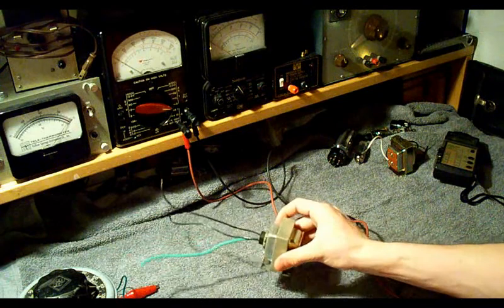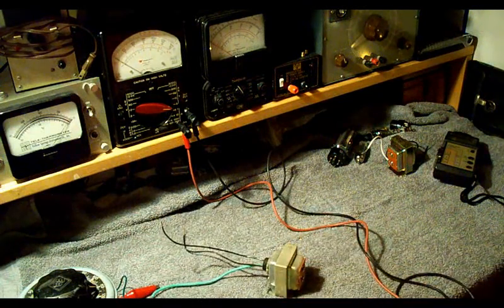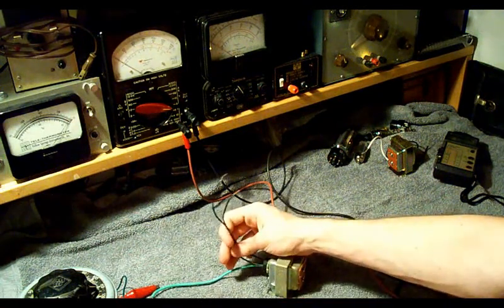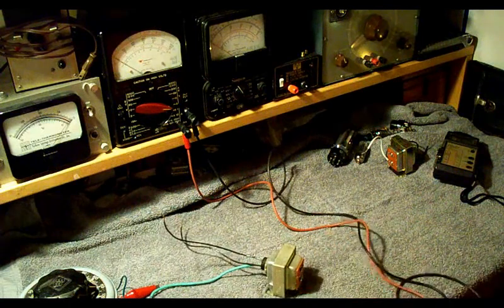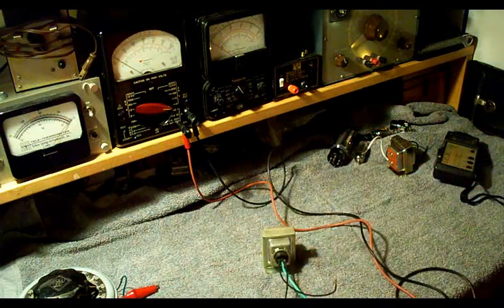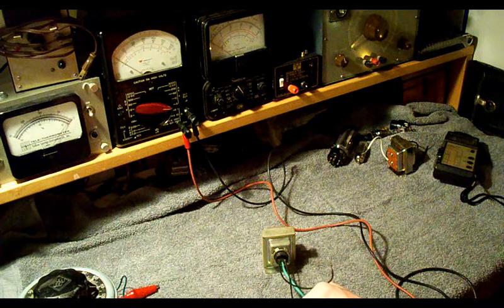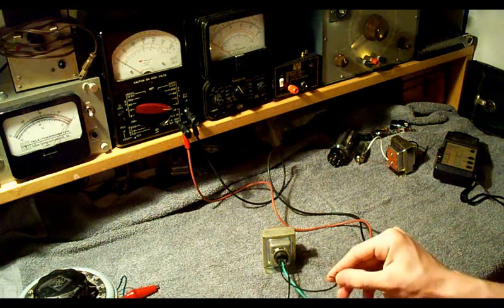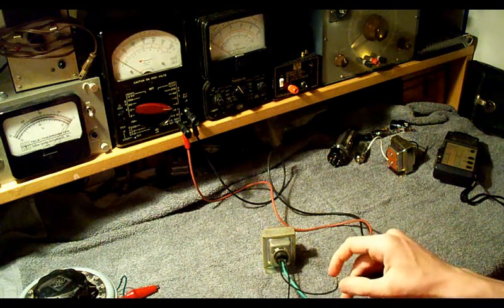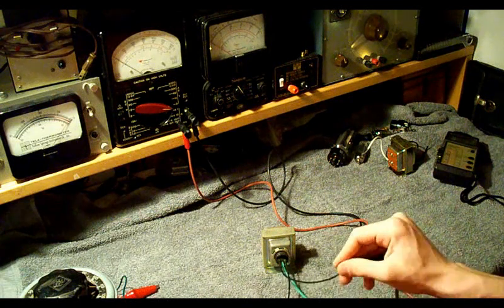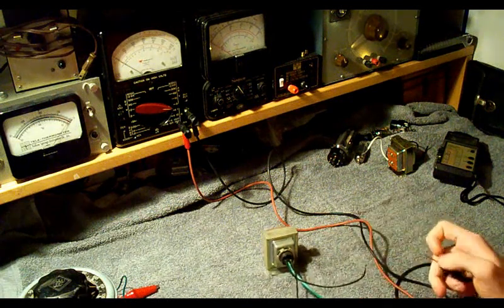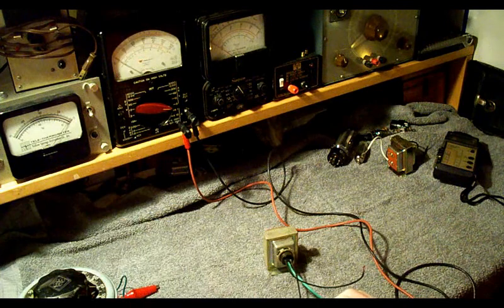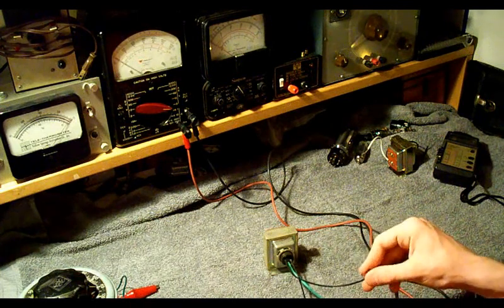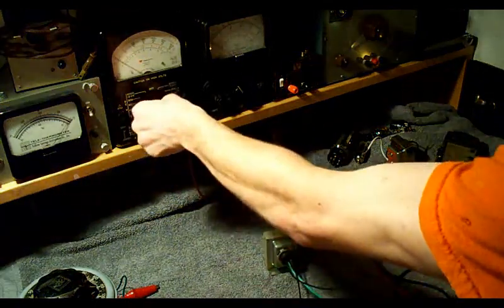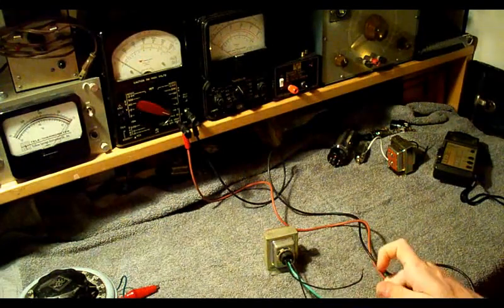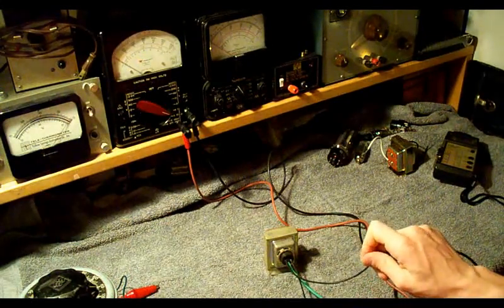Now let's test this one. Now this one is the same type of transformer. You get two wires for the primary and two wires for the secondary. So we'll start by checking to see if the primary is intact. We'll go one side of the primary to the other side. And we'll hook on there. And now I'm not getting any reading, so let me make sure. I got a reading last time, I believe. Let's check ×10 scale. This one might have a different resistance.